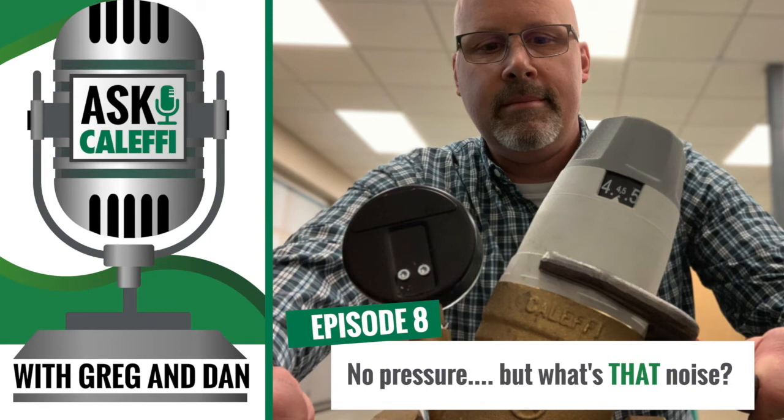The same thing can go for undersizing a valve — we get that on occasion too. Too much pressure drop is going to cause a lot of screaming of the valve — cavitation. We usually see that in much larger systems where they're stepping the pressure down way too much too soon. Typically you'll want to be within that two to one pressure ratio, never exceeding three to one. It'll operate at three to one, but it's highly recommended to stick closer to two to one.